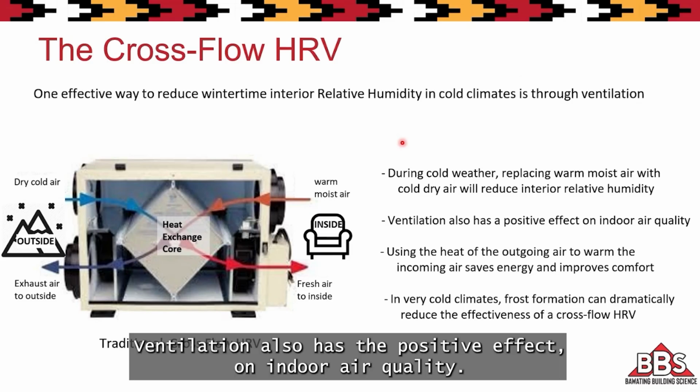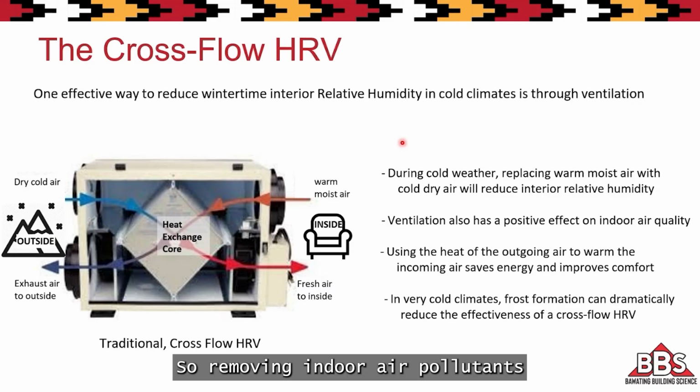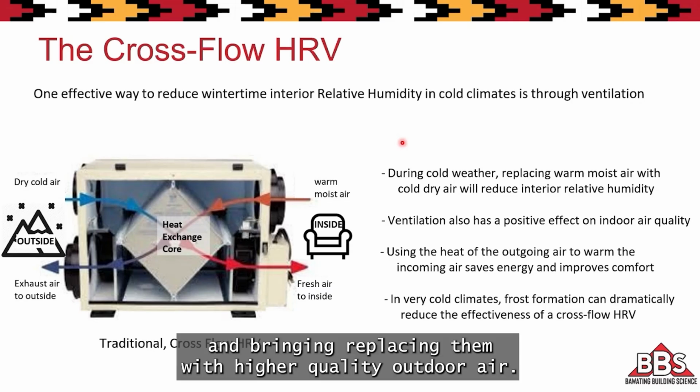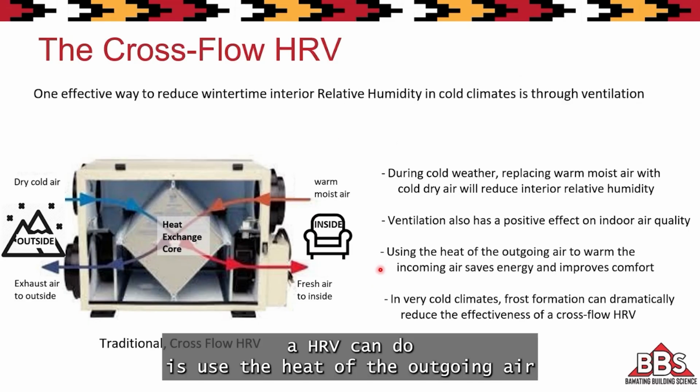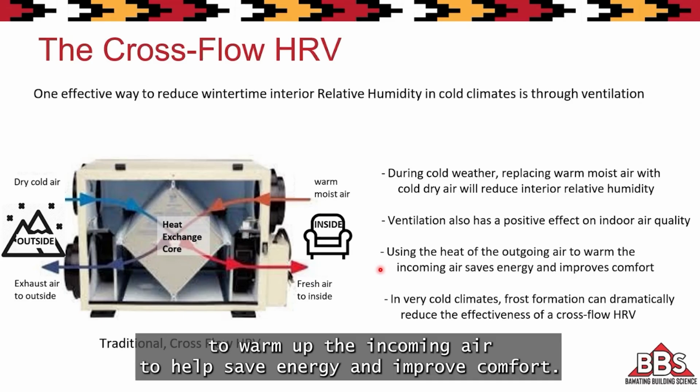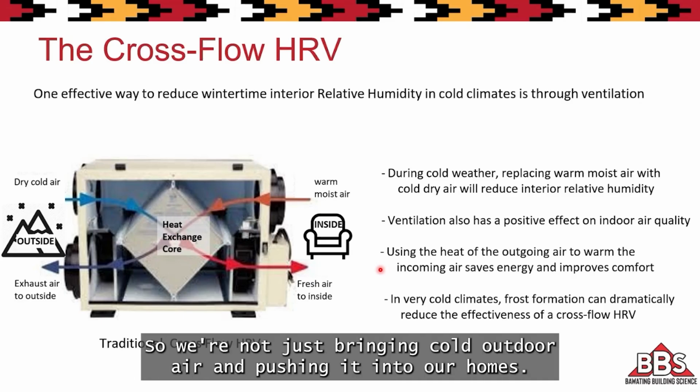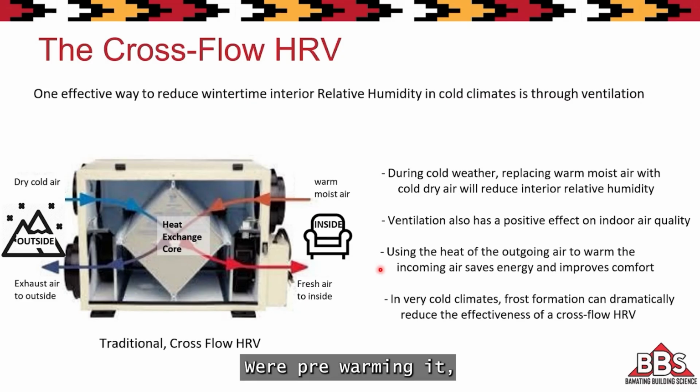Ventilation also has a positive effect on indoor air quality, removing indoor air pollutants and replacing them with higher quality outdoor air. And then what an HRV can do is use the heat of the outgoing air to warm up the incoming air to help save energy and improve comfort. So we're not just bringing cold outdoor air and pushing it into our homes, we're pre-warming it.